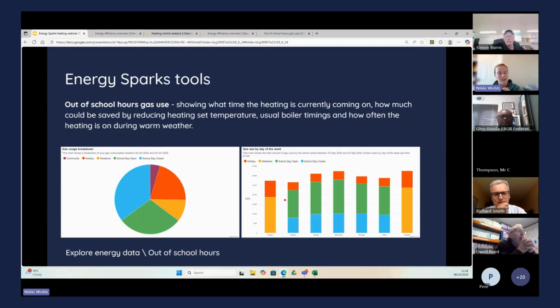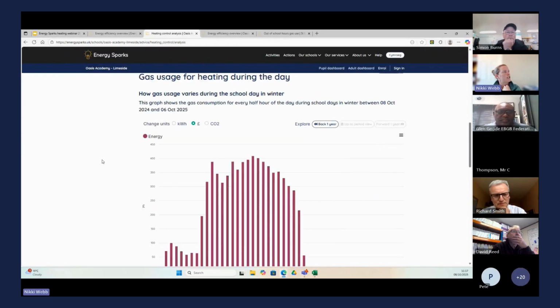So this school probably has their heating on as much in the holidays as in term time, and their heating was probably on more at weekends than during the week. This school has since made massive changes - they didn't realise the heating was coming on. I think this was a bad frost protection setting, so at the weekend their heating was just constantly on low rather than cycling, but not low enough I think. On weekdays it was coming on in the mornings and going off in the afternoons, but at weekends it was just constantly on. They've changed that, and by doing this they've saved something like 40% of their gas consumption over the last year. I'll show you this on these charts.